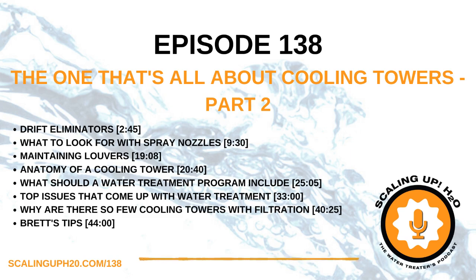We were just talking about the wet-dry evaporation - high concentrated solids water splashing over an area, maybe a nozzle is clogged, and now all those salts are exposed until it gets wetted again. Everybody thinks the scale means the water treatment chemistries aren't working, but it could be the nozzles are clogged. I've also seen people put variable frequency drives on their pumps and slow the water down so much that we're not getting good spray over the tower fill, and we see the exact same thing.